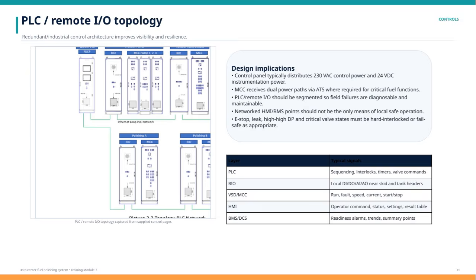Additionally, it's important that networked human-machine interface or building management system points are not the sole method for ensuring local safe operation. Hard interlocks or fail-safe mechanisms must be implemented for emergency stops, leaks, high differential pressure alarms, and critical valve states to guarantee safety and proper shutdown when necessary.